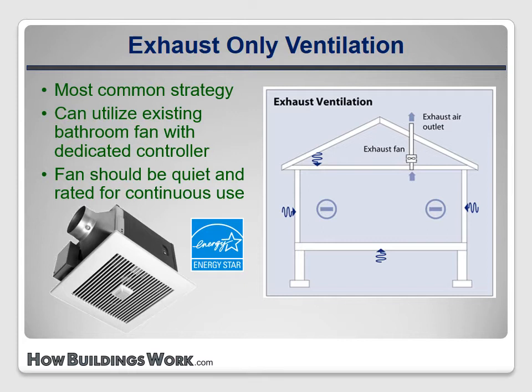This method is the most affordable option, but it has a few drawbacks. One is that there is an energy penalty associated with removing conditioned air and bringing in unconditioned air. Another is that the fresh air that enters may introduce unwanted moisture into building cavities, especially in warm, humid climates. And the last is that it ventilates the spaces around that bathroom very well, but it doesn't ventilate rooms that are far away very effectively.